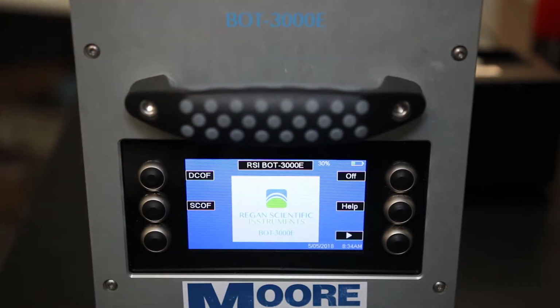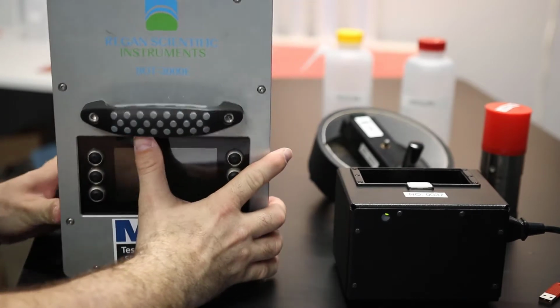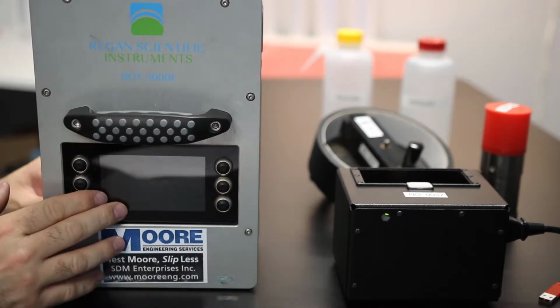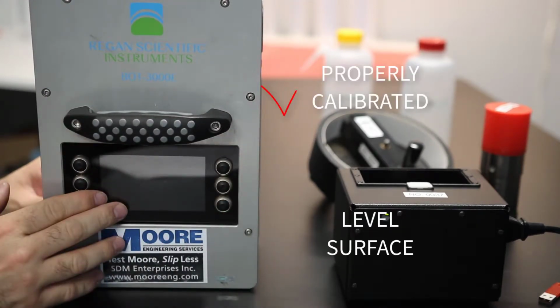Once you have determined your BOT-3000E tribometer has been calibrated within the past 365 days, you must verify the calibration by using the verification mass included with your BOT-3000E tribometer. To start this process, stand the BOT upright with the printer side down. In order for the BOT to pass verification, it must be both properly calibrated and on a level surface.